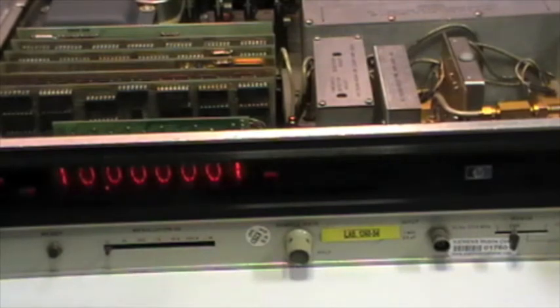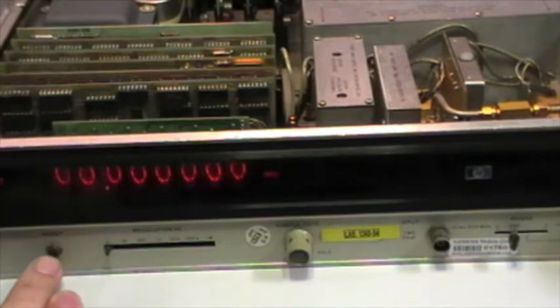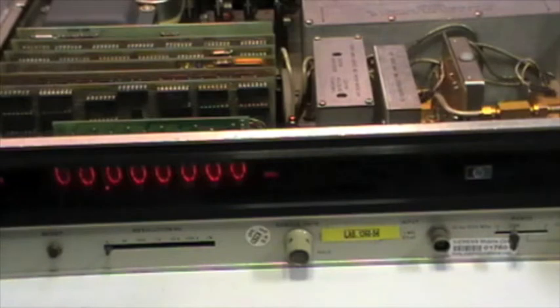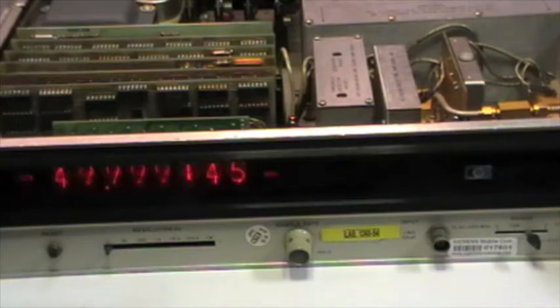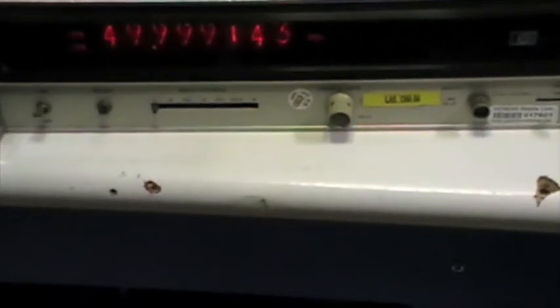For sure it will benefit from a contact cleaner treatment. However, reset, that does not work. Okay, so restart. It looks good so far. Move to the high frequency and see with my generator. So we are going to set, let's say, an amplitude of 200 millivolts, frequency 250 megahertz, and it's okay, 50, so perhaps it's not bad.